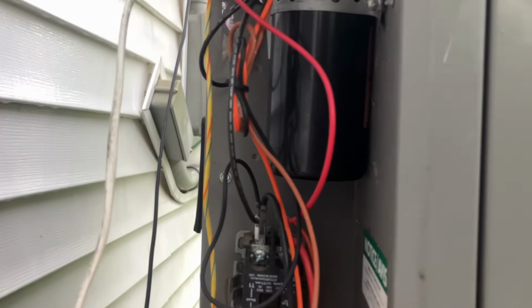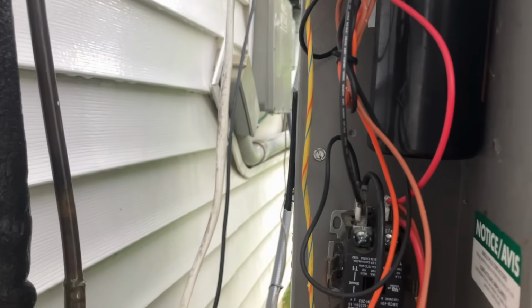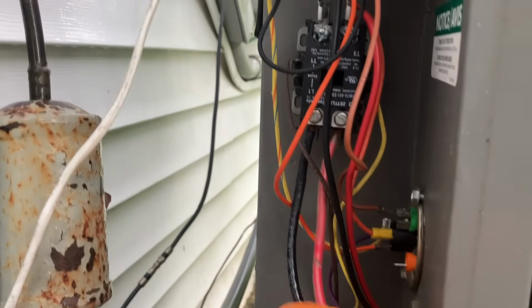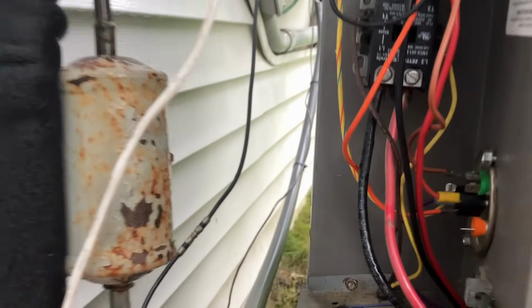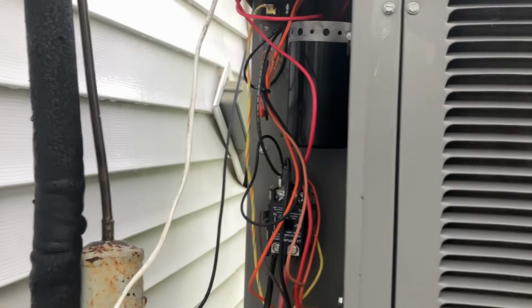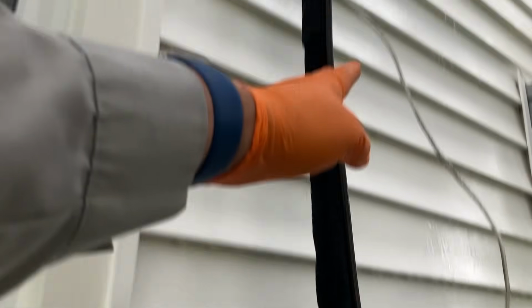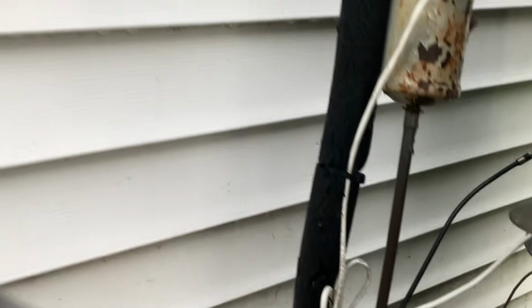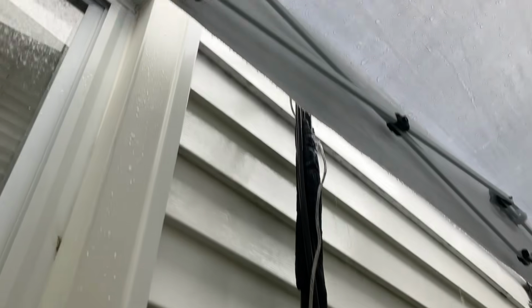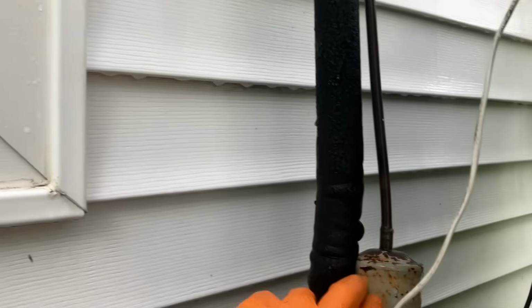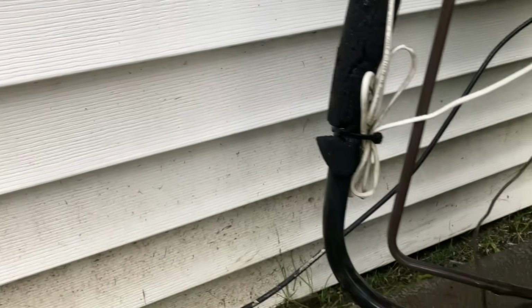We're just going to pull L1 and L2, the two lines of power, from the contactor, remove our ground, and remove the locking nut off of the liquid tight 90 right there. We'll save that and put it on our new unit. Obviously, we'll clean this up a little bit, clean up our line set, and put them behind covers as well. No filter dryer necessary. Hook that right up.